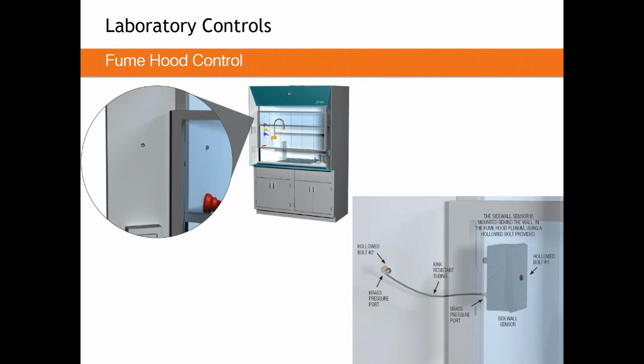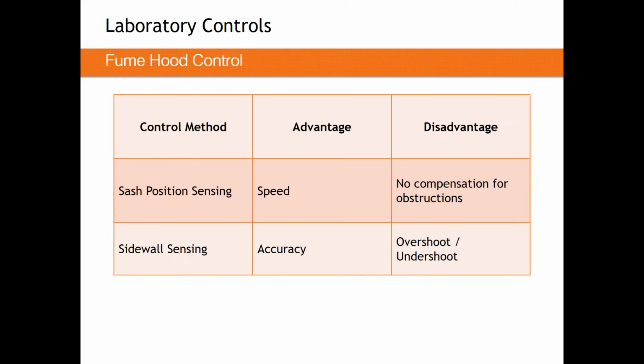It's a little bit slower than sash sensing. Sash sensing is, by the way, extremely quick. Sidewall sensing is a little bit slower, so instead of a 1 second speed of response, it can achieve a 3 second or less speed of response, but it is a bit more accurate because it's closing the loop for us. It's actually measuring the face velocity. So where sash position sensing is fast, it won't compensate for obstructions. So somebody standing in front of the hood won't affect sash position sensing. It's very fast and very, very stable.